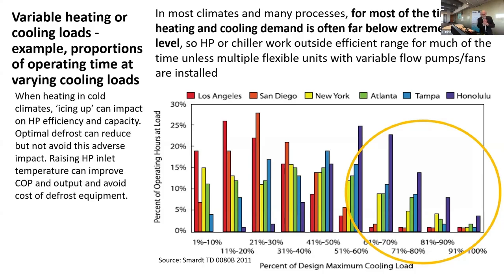One of the other big issues, particularly in cold weather, is icing up. If it's cold enough, the heat exchanger of the heat pump will start to not just condense water vapor from the air but actually freeze it, so the heat exchanger gets clogged up and you have to run the system backwards to melt the ice. You may also go more aggressively and run it backwards to avoid icing up altogether, but you're losing capacity at a time when the unit is already running at lower output because of the lower temperatures.